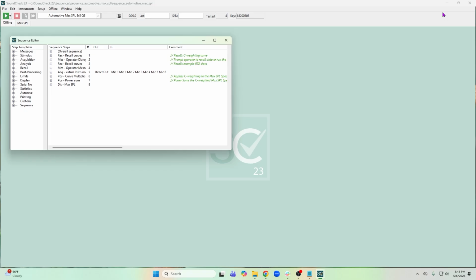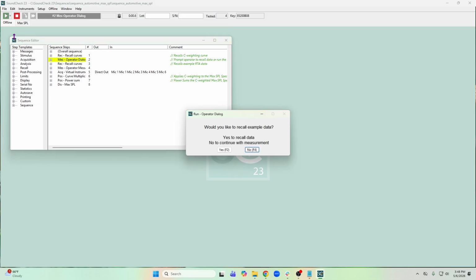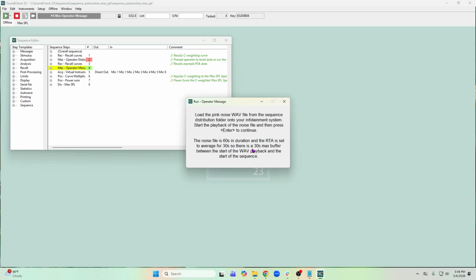I've downloaded the sequence from our website and changed it to a closed loop configuration as I'm playing the stimulus out of the 8x8. I did this by adding a signal generator to my virtual instrument acquisition to play the pink noise. I'll be using mics 1 through 6 and direct out 1 as my signal paths. These were created automatically and assigned to the appropriate hardware channels by SoundCheck. If you're running the sequence, be sure to read through the sequence notes as there are special instructions for gain settings and open loop configuration.